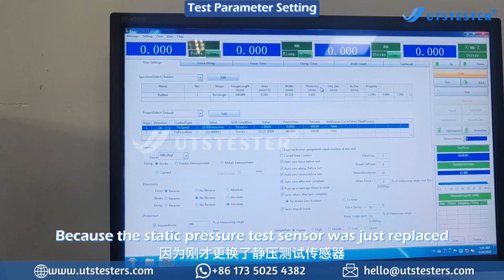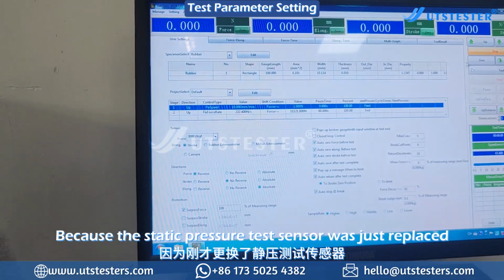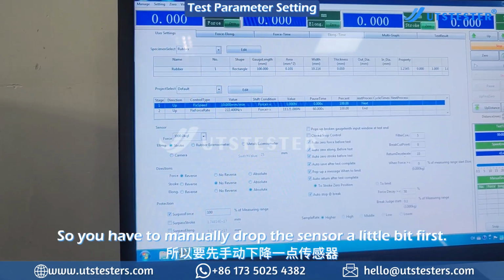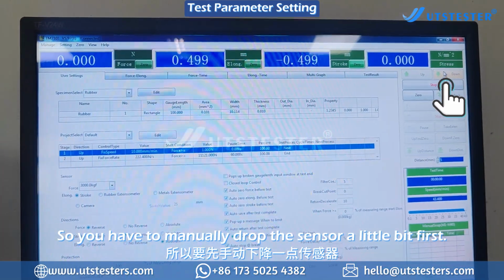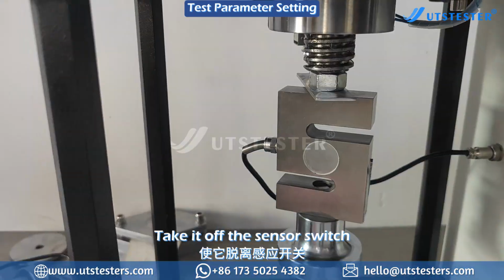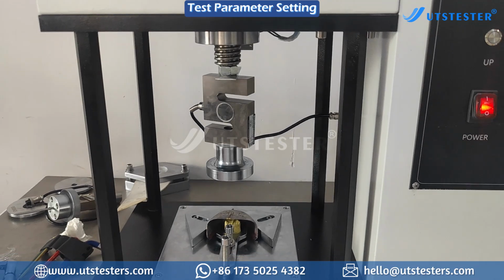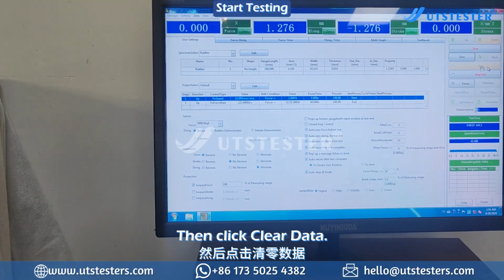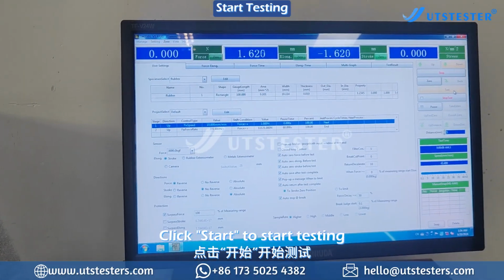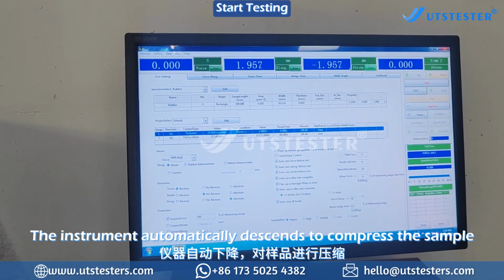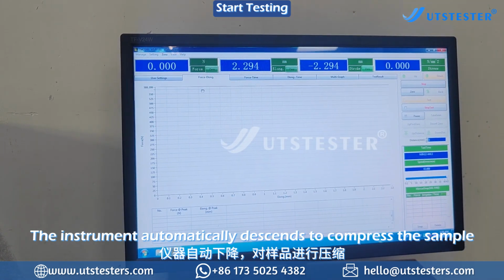Because the static pressure test sensor was just replaced, you have to manually drop the sensor a little bit first. Take it off the sensor switch. Then click Clear Data. Click Start to start testing. The instrument automatically descends to compress the sample.